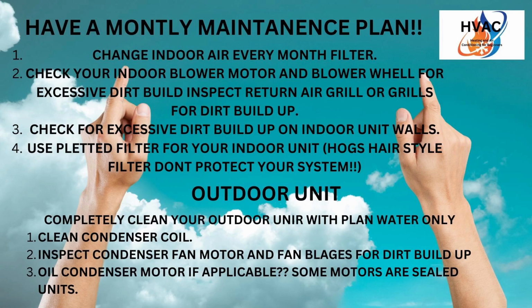But if it's mild, and you look at the other side where the blower wheel is exposed—since it's vented with open areas to keep it cool and isn't a sealed motor—you can take your vacuum cleaner with a hose and a little brush, go in there, run it, and clean the inside. Clean the walls too, and check for excessive buildup on the indoor walls.